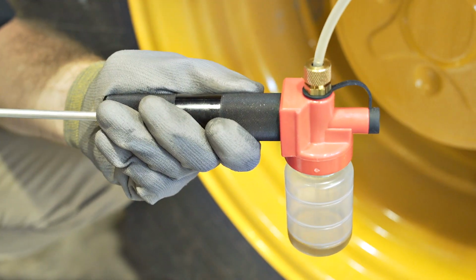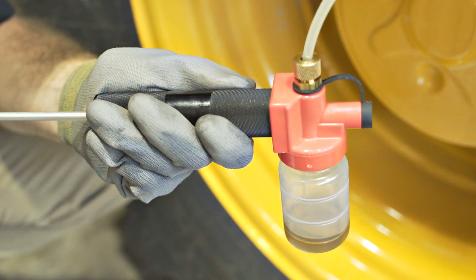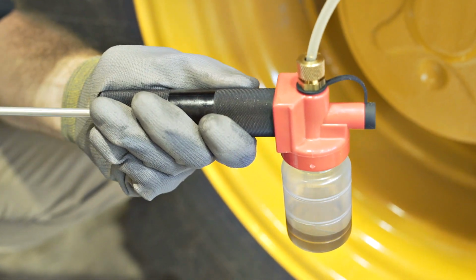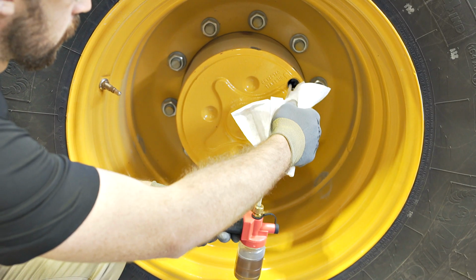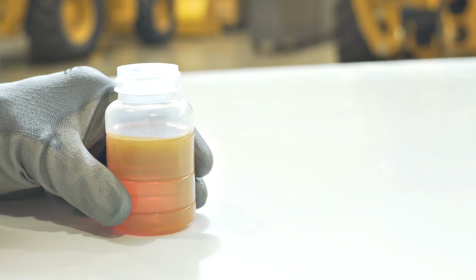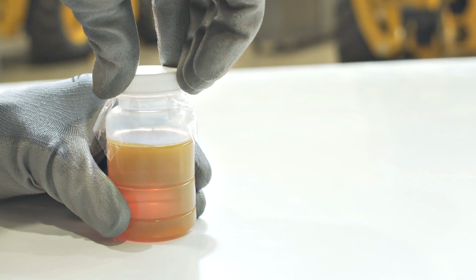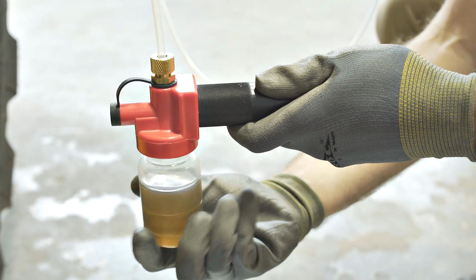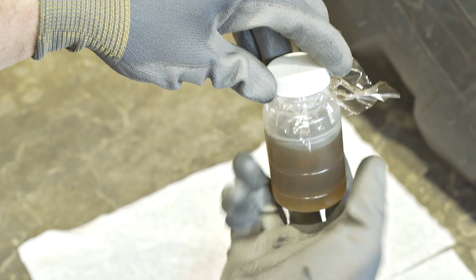Sample stationary equipment during normal operating conditions in return lines or downstream of pumps, cylinders, bearings, and gearboxes, and upstream from the filter. Do not take samples right after a filter change, on the outlet side of a filter, or after makeup oil has been added. Freshly filtered oil removes valuable information. Adding new oil dilutes the levels of contaminants and wear metals found, which may result in conditions appearing better than they actually are. Do not reuse sample probes.